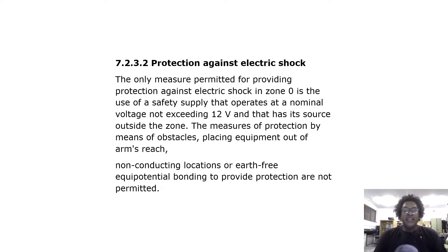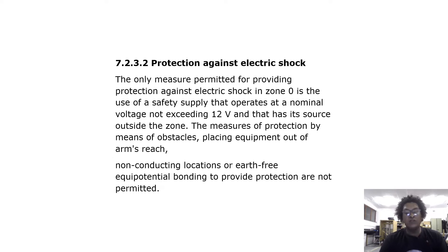The only measure permitted for providing protection against electric shock in zone 0 is the use of a safety supply that operates at a nominal voltage not exceeding 12 volts and that has its source outside the zone. The measures of protection by means of obstacles, placing equipment out of arm's reach, non-conducting locations, or earth-free equipotential bonding to provide protection are not permitted.